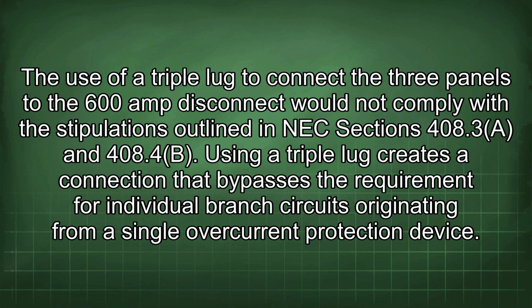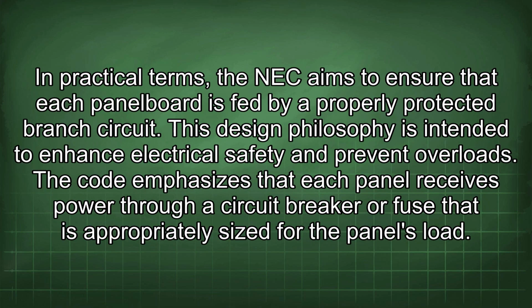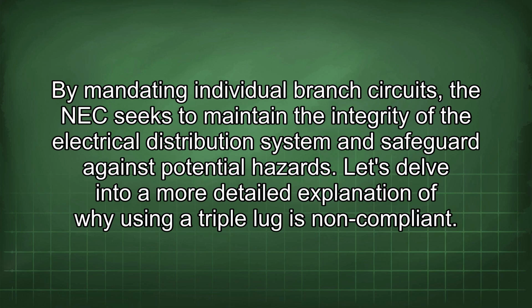Using a triple lug creates a connection that bypasses the requirement for individual branch circuit originating from a single overcurrent protection device. In practical terms, the NEC aims to ensure that each panel board is fed by a properly protected branch circuit. This design philosophy is intended to enhance electrical safety and prevent overload. The code emphasizes that each panel receives power through a circuit breaker or fuse that is appropriately sized for the panel's load. By mandating individual branch circuits, the NEC seeks to maintain the integrity of the electrical distribution system and safeguard against potential hazards. Let's delve into a more detailed explanation of why using a triple lug is non-compliant.